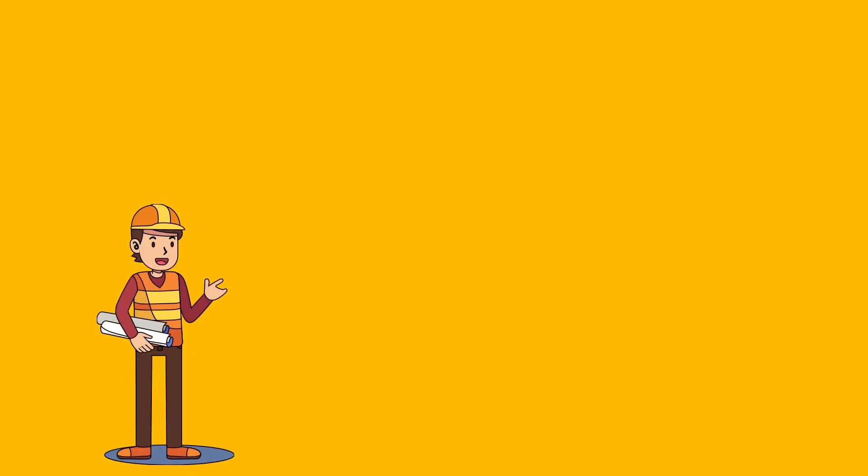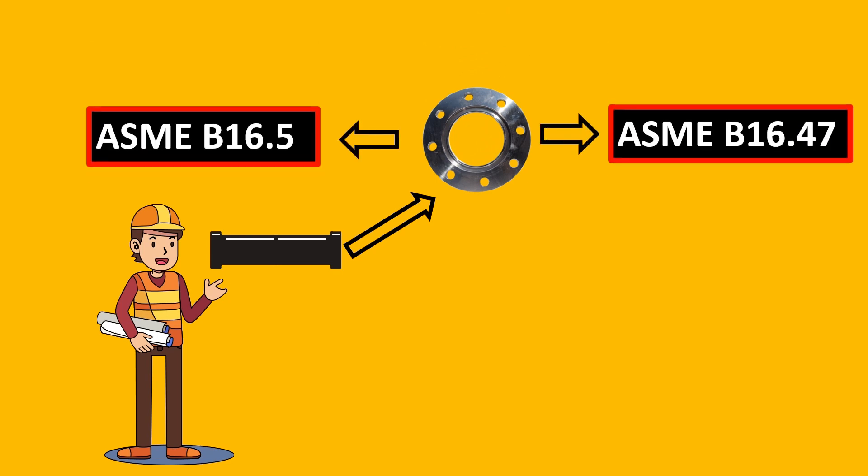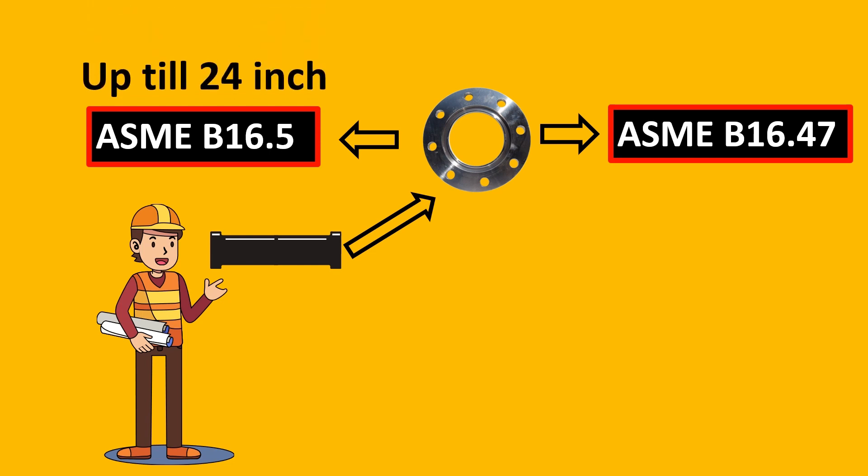So here we look today at the flange standard. For an on-off valve, there are only two flange standards available: ASME B16.5 and B16.47. It is very simple: B16.5 is used up to 24 inches, and B16.47 goes from 26 inches and above.